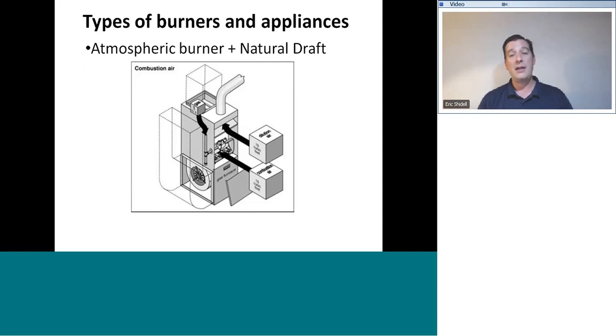So the solution in that case was to go down to the supply house, get another section of double wall vent pipe, and raise the vent, make it longer. Problem solved. And we actually had to end up doing that in several units in that building to overcome that challenge. That's the stack effect. It's a really neat natural phenomenon that happens with a vertical section of pipe going from inside a building to outside. It's a constant draw.